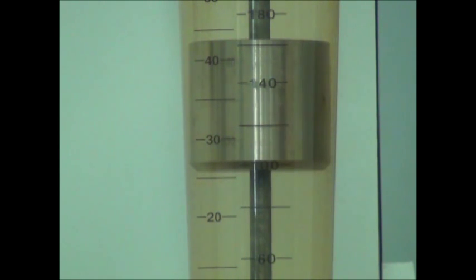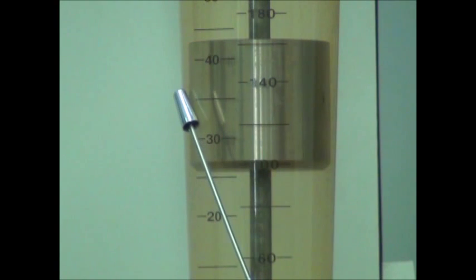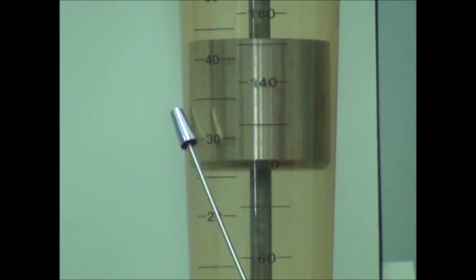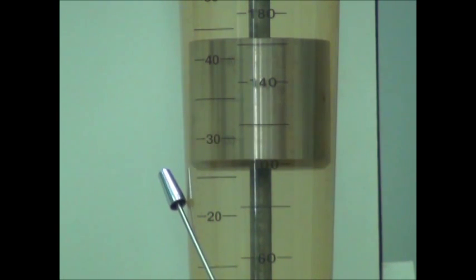So we've plotted our values on the pump curve. We've predicted a flow of 42 gallons a minute. Let's look at the flow meter. You can see that we're right between 40 and 45, maybe a little closer to 43. As you can see, we've come very close to the number that we predicted by using the gauges and the pump curve.